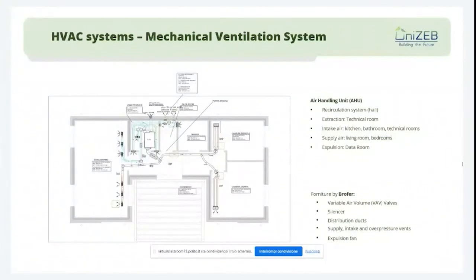So with the blue lines you can see there are some blue pipes coming and going to the kitchen and the bathroom. The red ones go to the bedrooms, the single and double bedroom, and also the living room. Although it's an open space, and you may think there would be interference between the supply and return side, we found the design was sufficient to avoid interference between the two circuits, and that it was actually necessary to have both the supply and extraction side there, because the space is quite wide. So it was preferable to have this double solution.